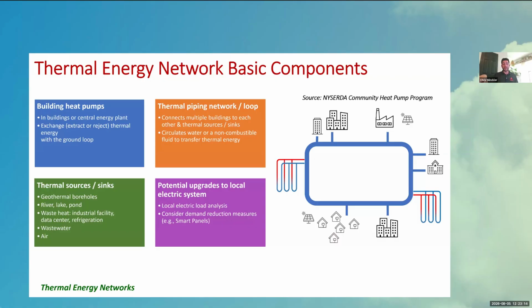Where for that same 2,000 square foot house, a lot of times we can get away with a single 500-foot borehole, and that borehole is only 6 to 8 inches in diameter and takes up a very tiny footprint. So as we start looking at either bigger homes or in most cases cities, it's just much less space required to get the thermal capacity that we need.